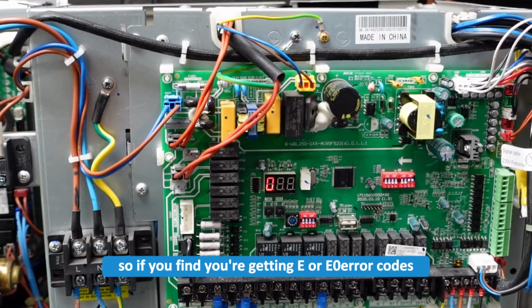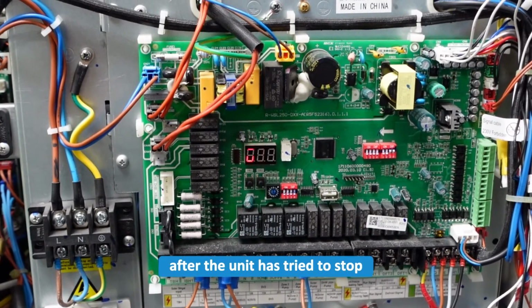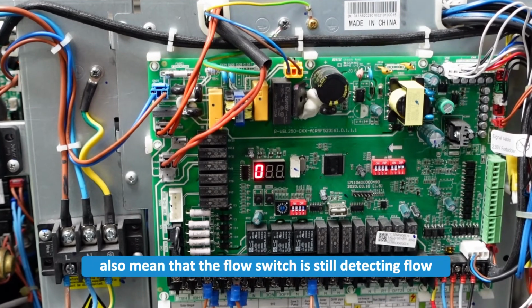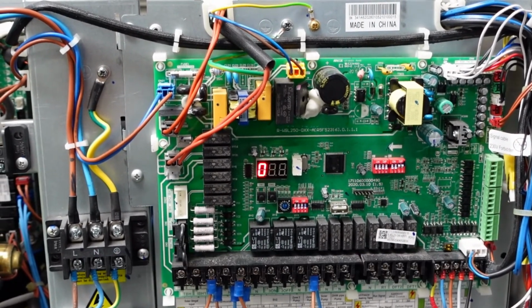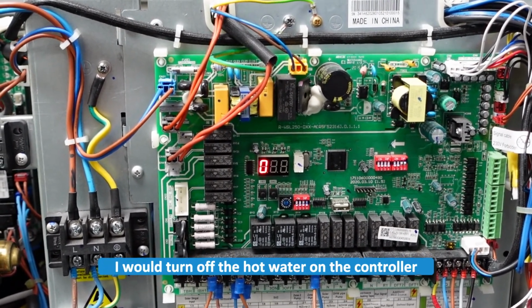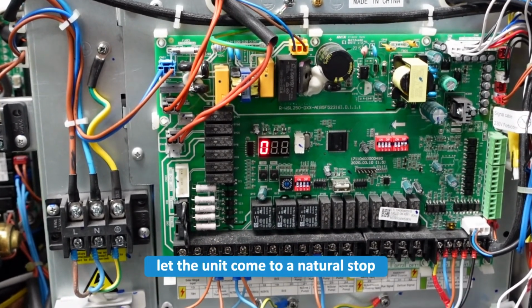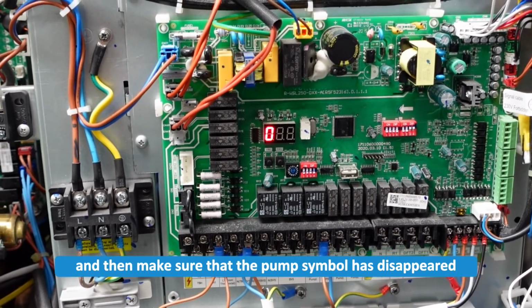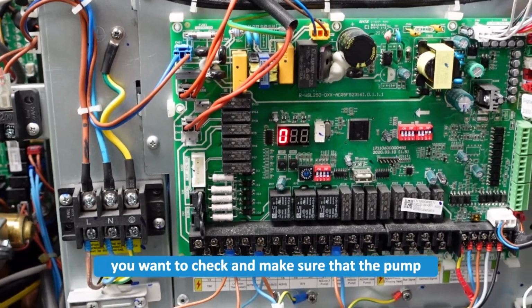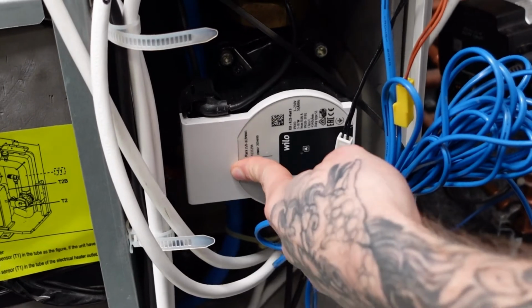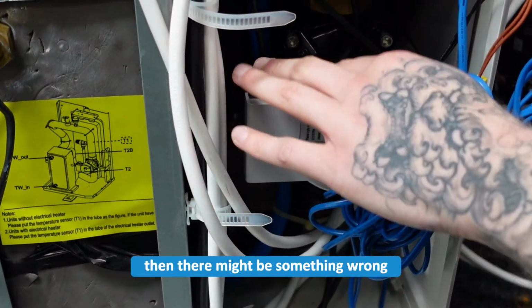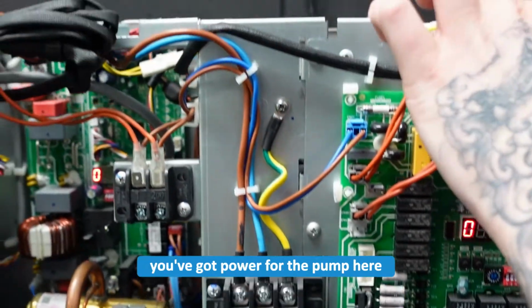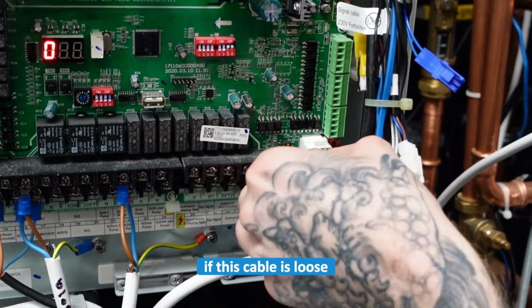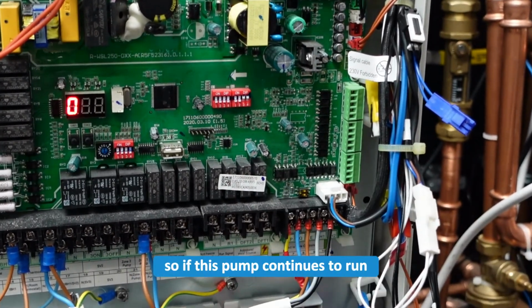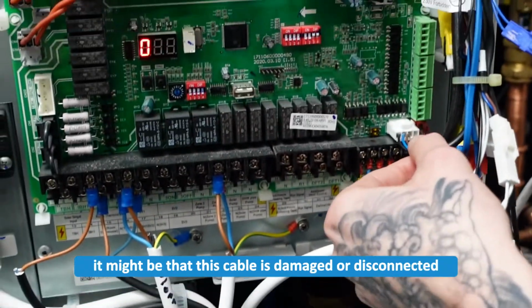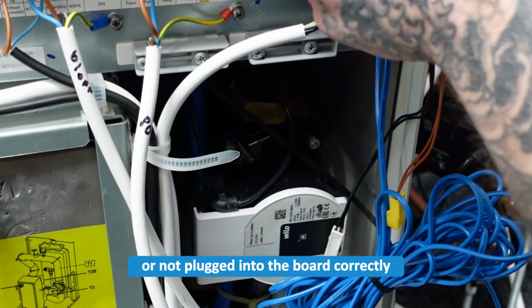So if you find you're getting E8 or E0 error codes after the unit has tried to stop, E8 can actually also mean that the flow switch is still detecting flow when the unit thinks that the pumps should all be off. So in that instance, I would turn off the hot water on the controller and kill all the heat in demand, let the unit come to a natural stop, and then make sure that the pump symbol has disappeared off the controller. Once the pump symbol has disappeared off the controller, you want to check and make sure that the circulation pump in the unit has actually stopped. If it is continuing to run, then there might be something wrong with the way that it's connected onto the PCB. You've got power for the pump here, and the PWM control cable is here. If this cable is loose, the pump will run flat out all the time. So if this pump continues to run after you've tried to stop the heat pump, it might be that this cable is damaged or disconnected or not plugged into the board correctly.